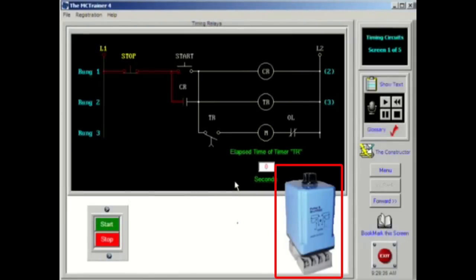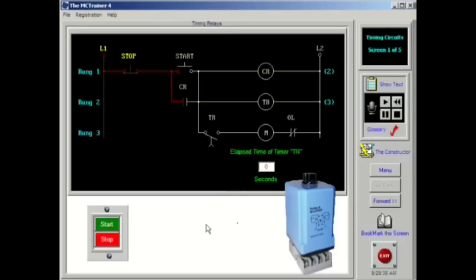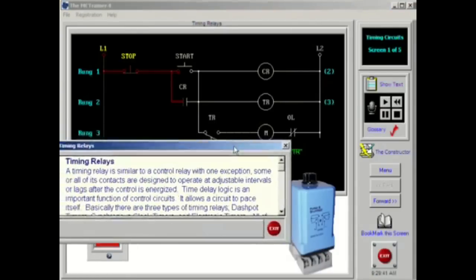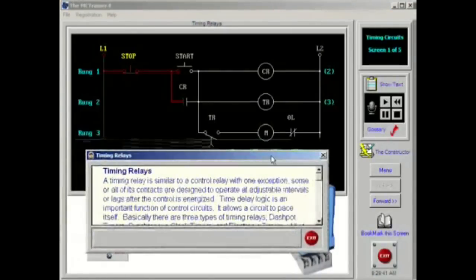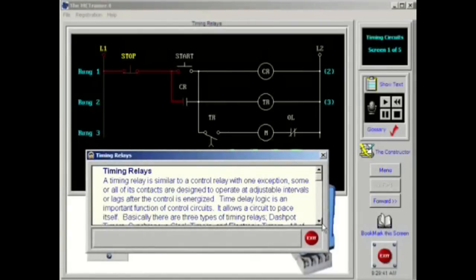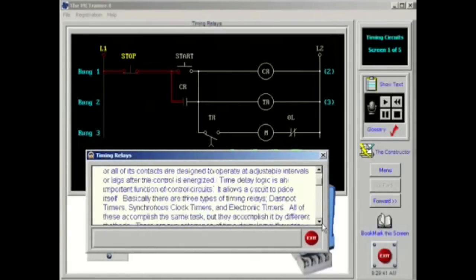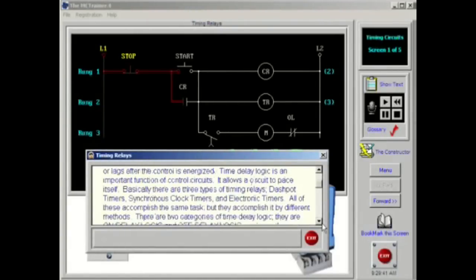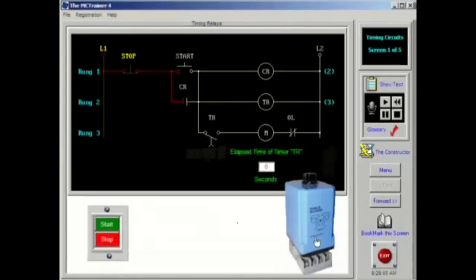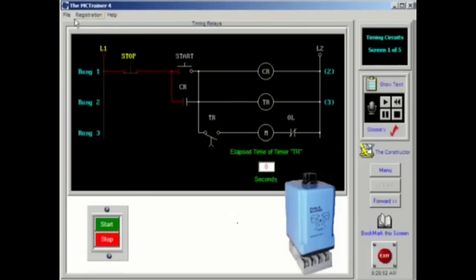A timing relay is similar to a control relay with one exception. Some or all of its contacts are designed to operate at adjustable intervals or lags after the control is energized. Time delay logic is an important function of control circuits. It allows a circuit to pace itself.